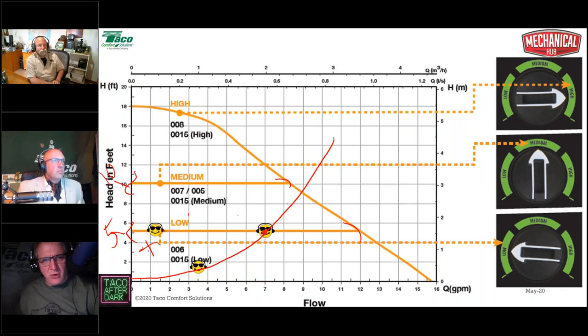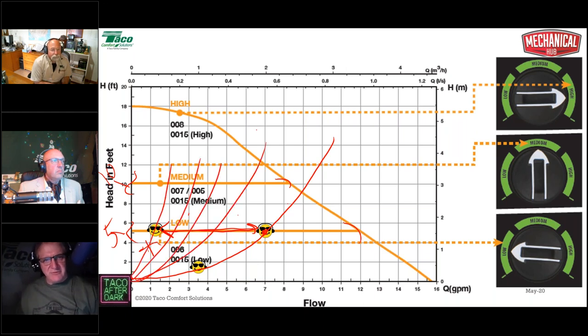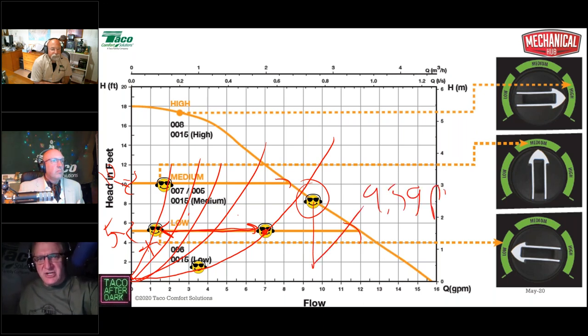Now, as these zones open, we're going to go that way. As the zones close, we're going to go that way, as the system curves intersect the performance curve. All right. Now, if for giggles and grins, we said, I don't know where to set it, I'm going to set it in the middle. I'm going to put it on the 10-foot head constant pressure line. Well, now I'm working way out here where the system curve intersects. Look at that, 9.5 GPM, just like we had before. All right. And my one single zone, I'm going to be at a shade less than 2 gallons a minute.